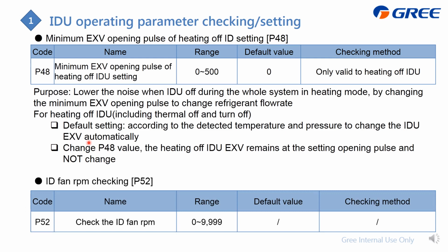And the next is how to check the indoor fan RPM, and this is only for the DC fan motor, and the code is P50. Then you can change the code to P52, and it will display the fan RPM directly on the wire controller.